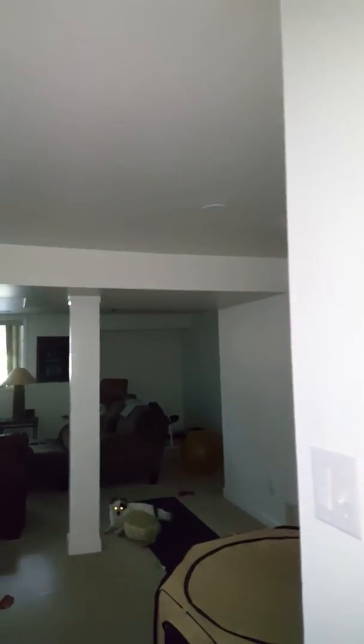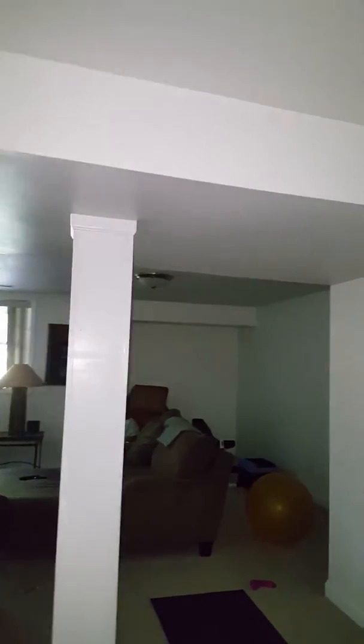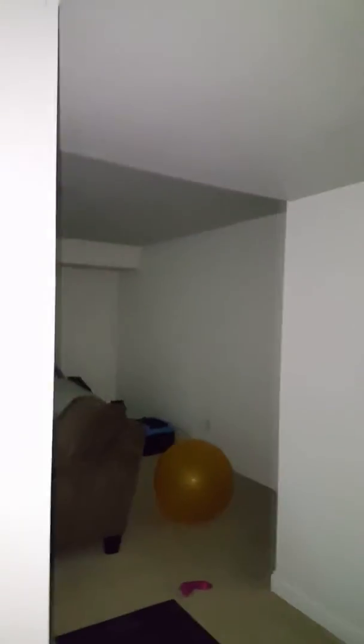We're on a 40-amp breaker which is marked — make sure that's correct. Above that ceiling right there is your combustion grill. We're actually gonna have to go above the ceiling over there. There's your one access hole, but it actually leaks water because it has no insulation, and that's an access door to the back side of everything.